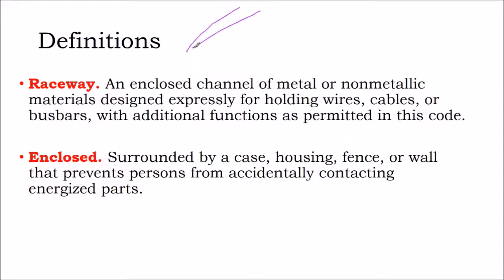So here's your rafter, here's your solar panel, and building integrated solar you can do with the existing products that are out there on the market. But the problem with building integrated solar is that now you have these cables coming off the underside of the module. And what we'll see a bit later is direct current circuits must be in an enclosed metal raceway. So if you have these exposed circuit conductors that are not fully enclosed in a metal raceway, then you're just asking for a code violation.